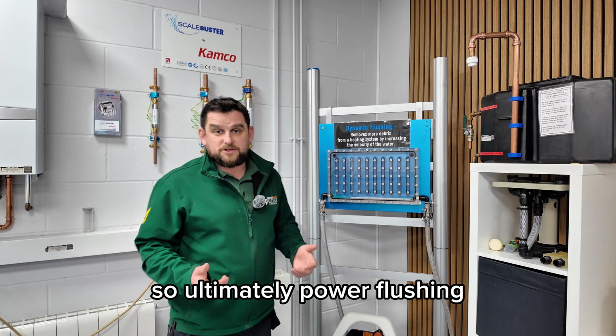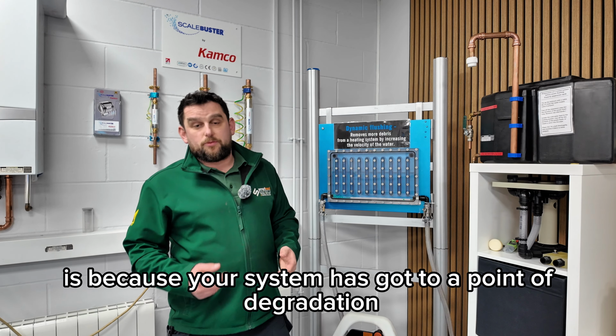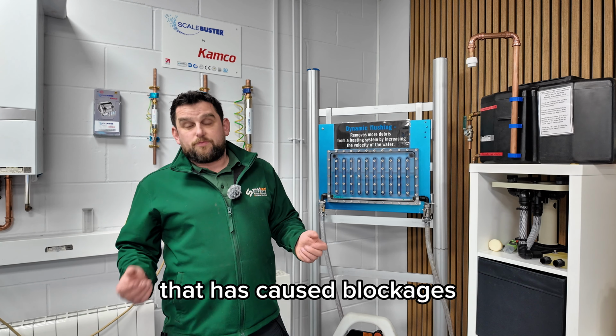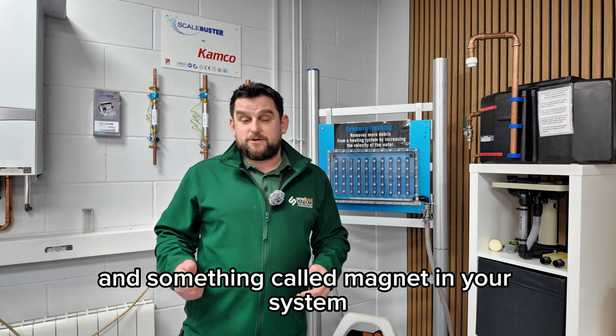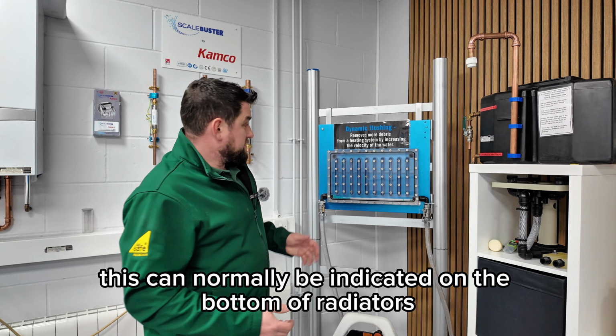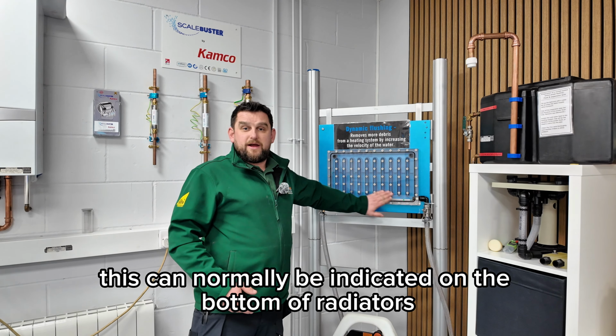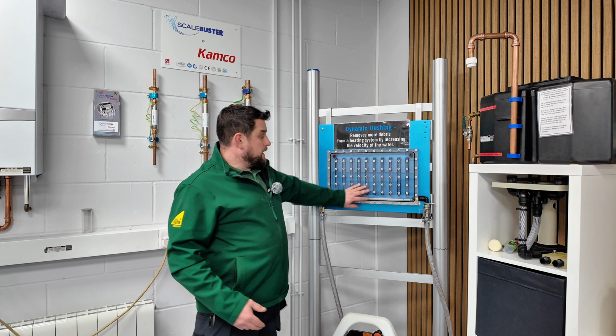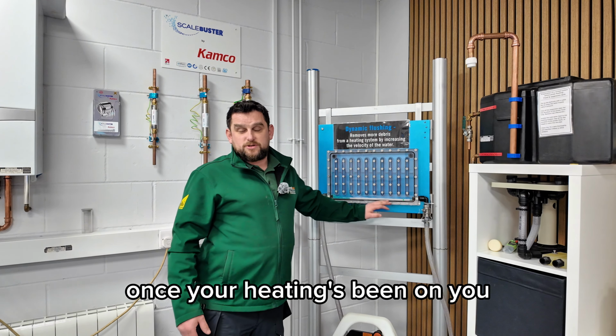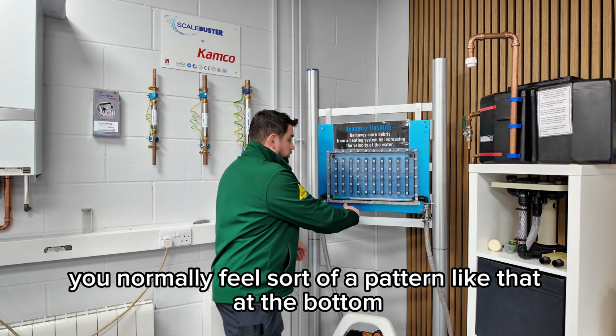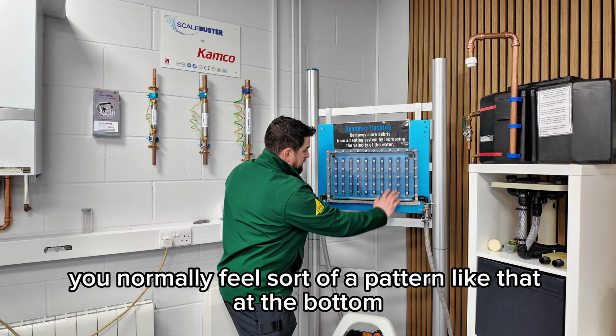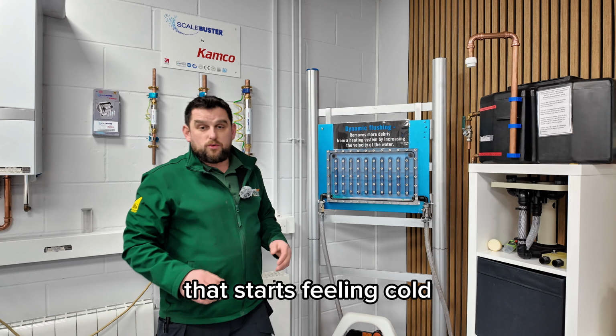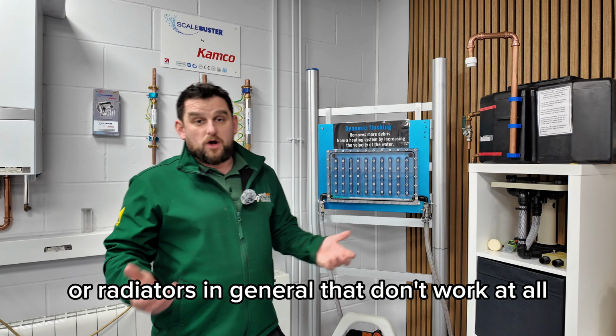Ultimately, power flushing is needed because your system has got to a point of degradation that has caused blockages and something called magnetite, stopping the flow. This can normally be indicated by cold spots on the bottom of radiators. If you feel the bottom of your radiators once your heating's been on, you'll normally feel a pattern that starts feeling cold, or radiators that don't work at all.